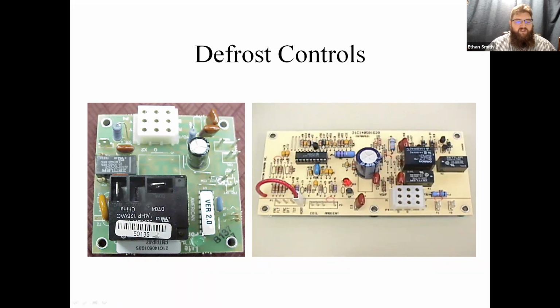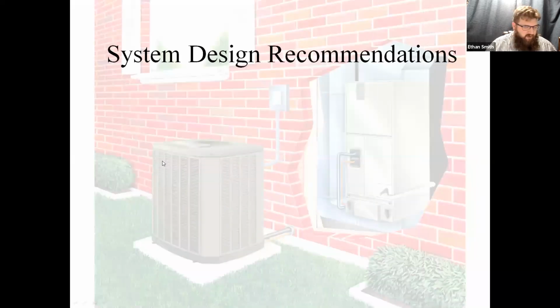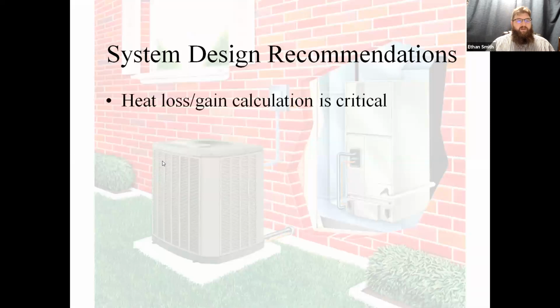And then of course we get a version number on these things. So we'll go into that a little bit. Successful heat pump installations rely on a number of different things, guys. First of them is you've got to have an accurate heat loss or heat gain calculation in order for these things. And so if you don't have that, your system's not going to work in cooling, and it's going to have the added feature of not working even worse in heating mode.